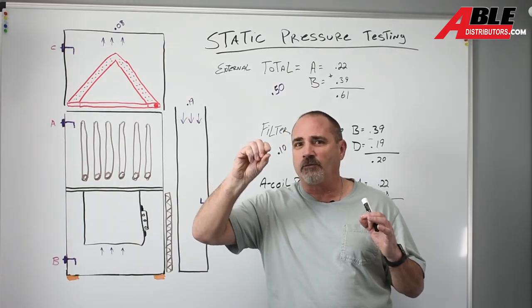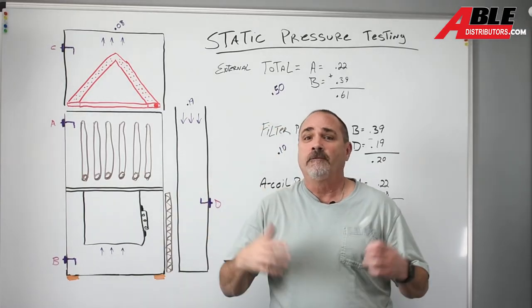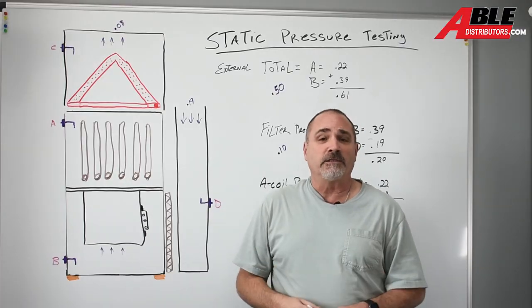Changing out return grills to where the spacing is 3/16th of an inch instead of an eighth of an inch. So if you get a house where it's an eighth of an inch and it's been painted 15 times over the last 20 years, that could be some of your issue right there.